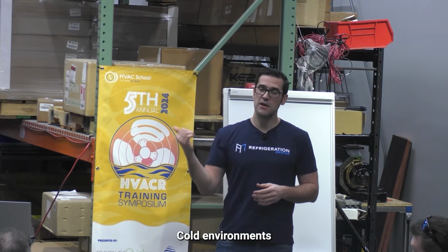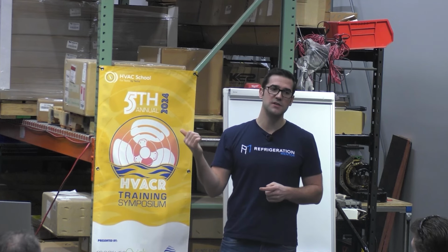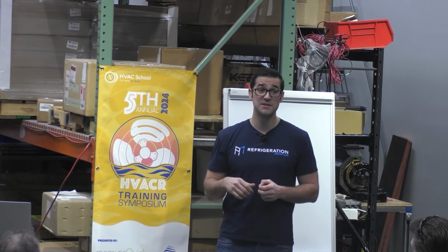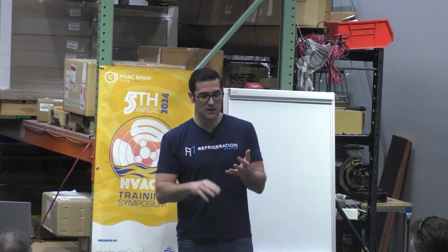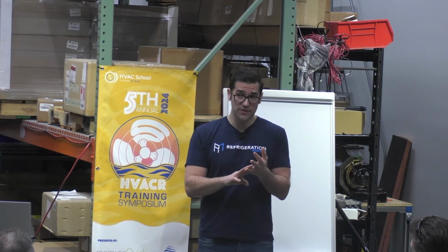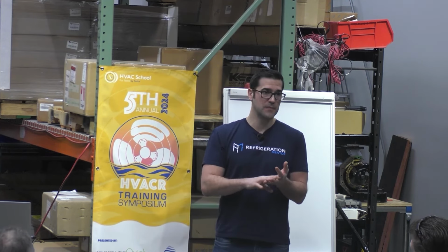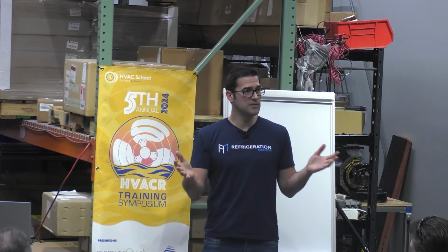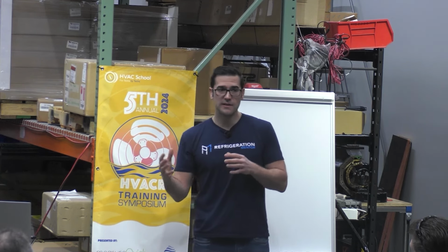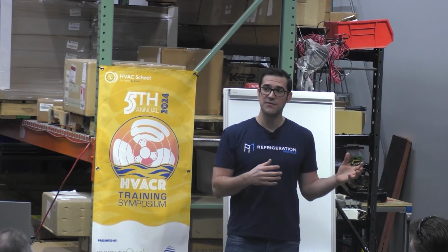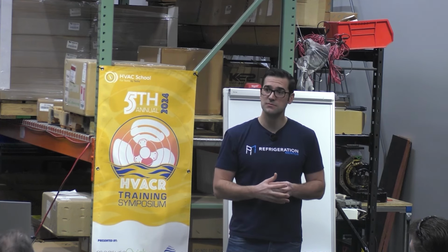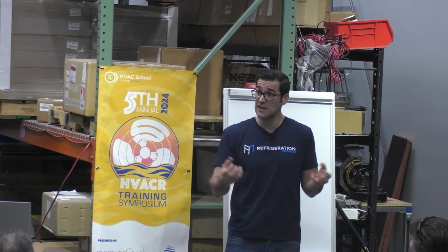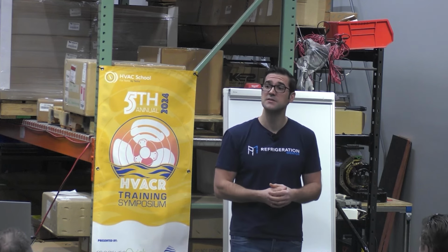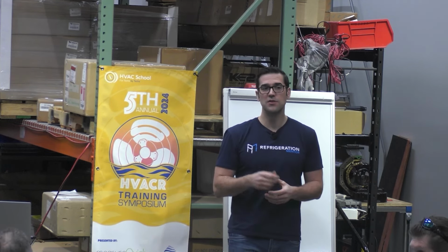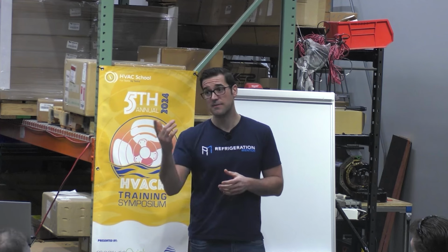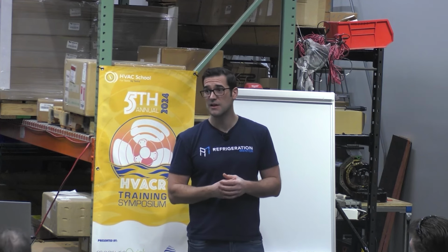Another thing that people don't look at for CO2 is that it'll pull down a system way faster. Compared to an A2L or even A3, which is very good, or an HFC, take ice rinks. I'm working with a lot of people doing ice rinks. They're pulling down the ice in half the time compared to what they used to do, just because of how efficient the heat transfer is. I can pull the heat out faster, and you're using smaller pipes. Depending on the comparison, but that's really what it is. You can get a lot of heat out of CO2.